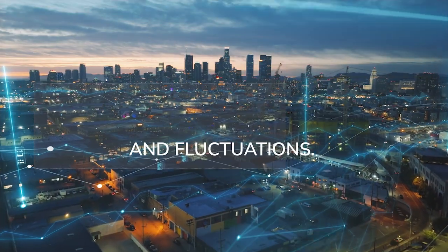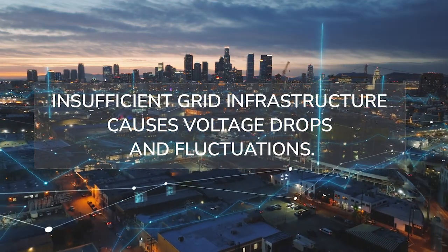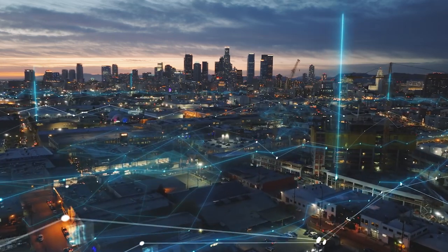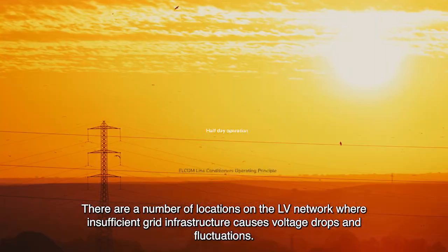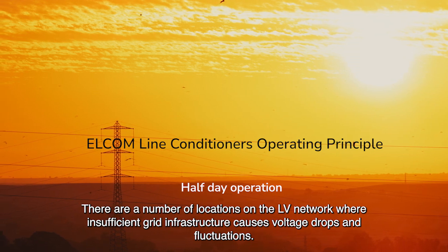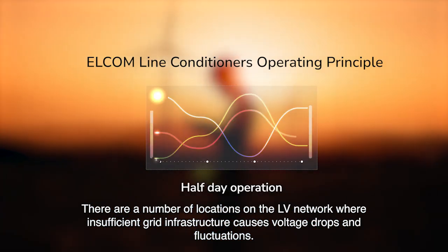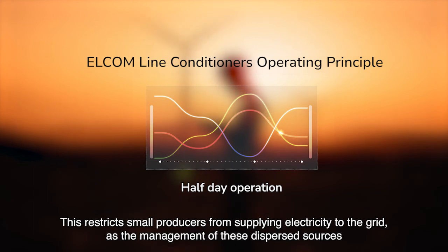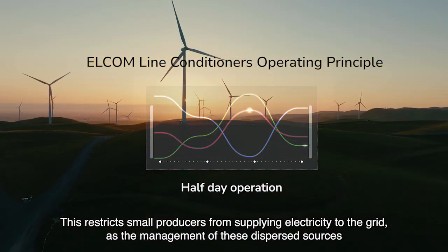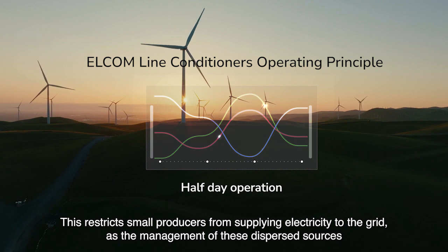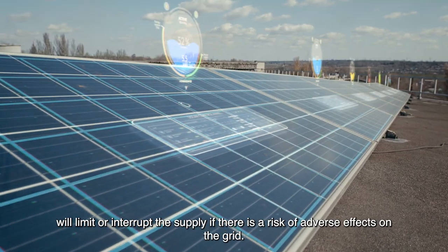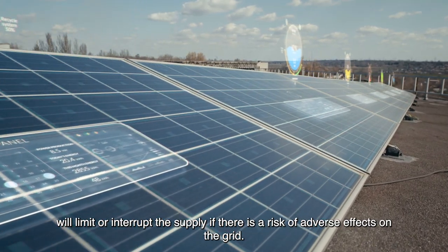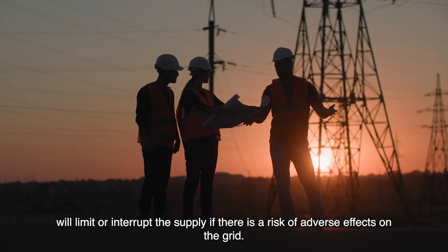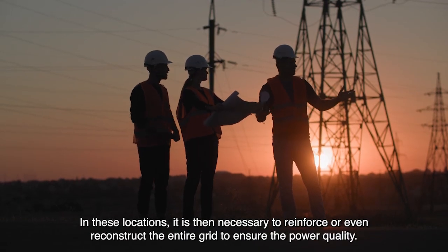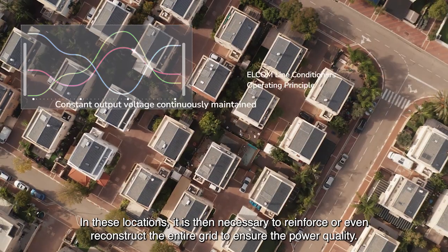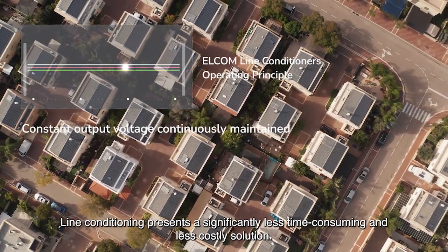Insufficient grid infrastructure causes voltage drops and fluctuations. There are a number of locations on the LV network where insufficient grid infrastructure causes voltage drops and fluctuations. This restricts small producers from supplying electricity to the grid, as the management of these dispersed sources will limit or interrupt the supply if there is a risk of adverse effects on the grid. In these locations, it is then necessary to reinforce or even reconstruct the entire grid to ensure the power quality.